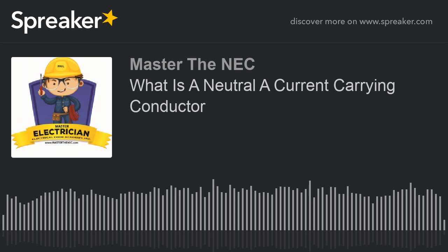Again, I don't have to add but one of them. I don't have to add them both in that application, because they're both not going to be energized at the same time. But now, when it comes to raceway fill, I count them both because it takes up space. But when I come to current carrying conductors, I don't. At any given time, it might be a current carrying conductor, but they both aren't going to be at the same time. If they were, you'd have a dead fault, and of course, nothing would work anyway.